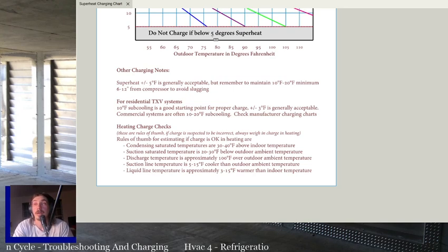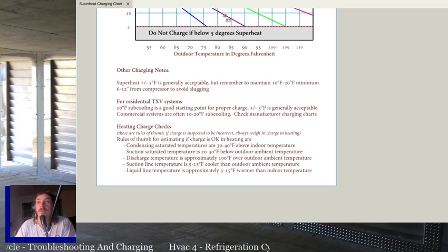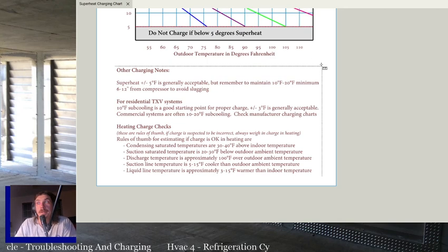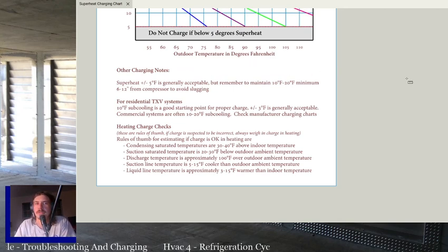And if you ever don't have superheat, if you got compressor sweating, or you don't have superheat 6 to 12 inches from the compressor, you should probably be pulling out charge until you figure out what's going on. But diagnose everything else you can first. But yeah, if you got sweating, figure out why you got it. It's probably not the charge, but it could be overcharged so bad that it's got no superheat, and that's not a good thing.